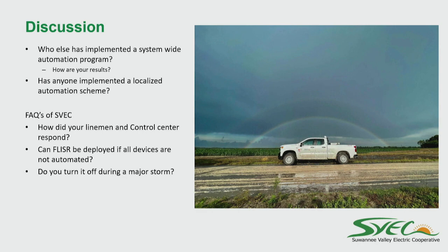But if it's under a fault condition, one phase can trip and lock out, because we're so rural, mostly residential, it doesn't make a lot of sense to drop all three phases if we have the ability to just drop one. We didn't have a lot of imbalance issues, but you can program it to look for all these different indicators, and you also have to remember there's a mixture now, because you're not doing localized control. There's what your overall entire system needs to do, what this area needs to do, what this single relay needs to govern and watch for.